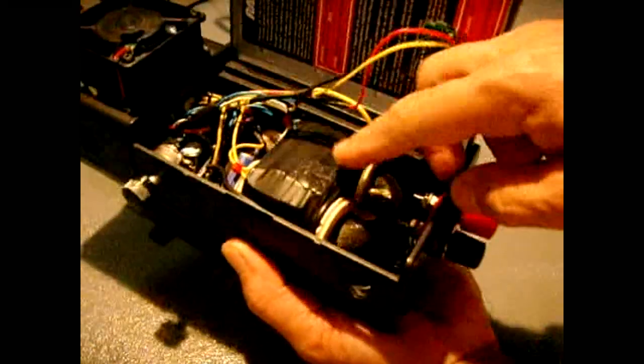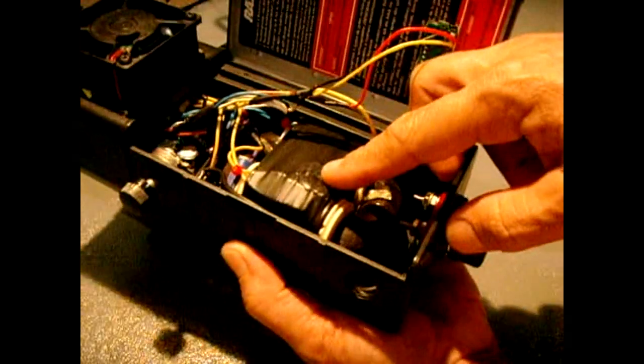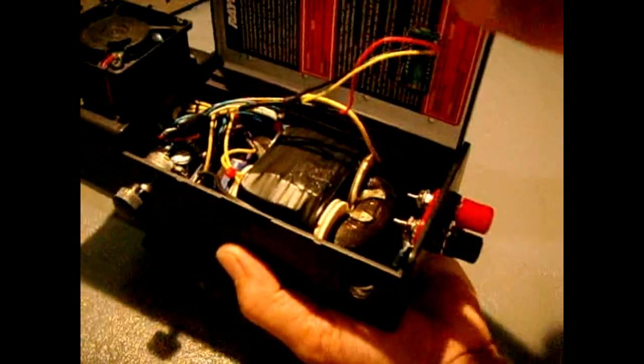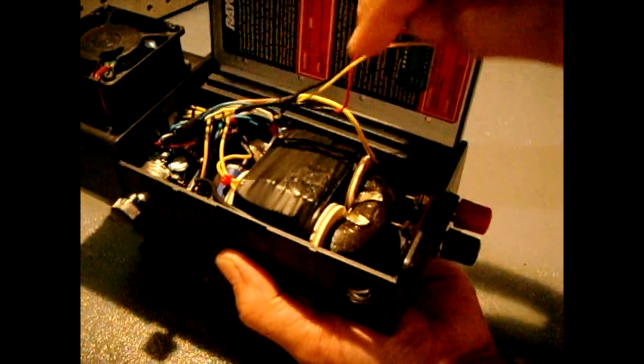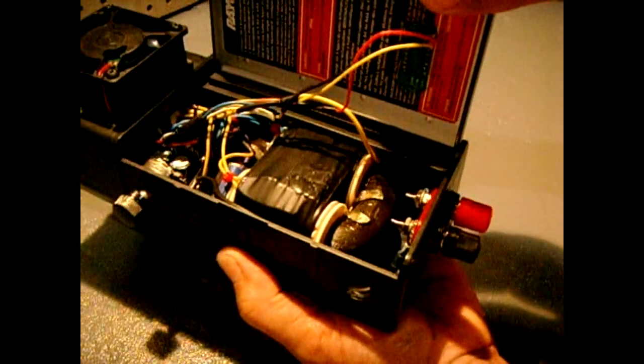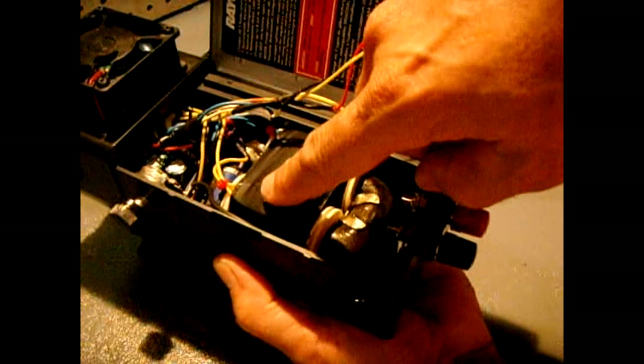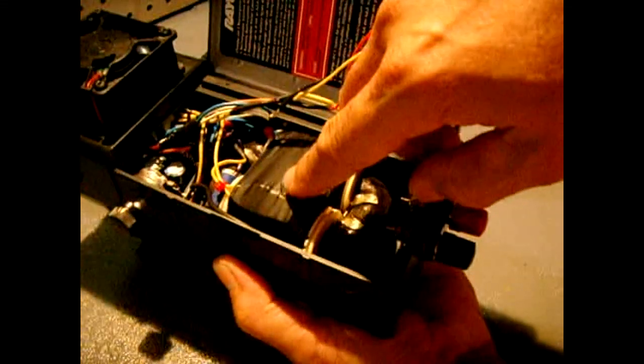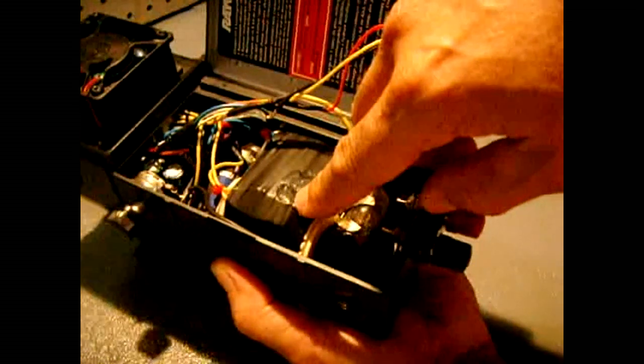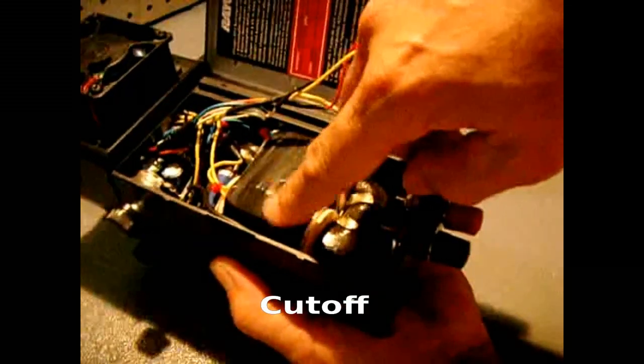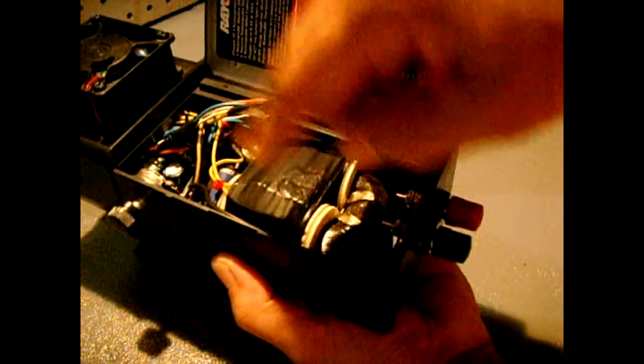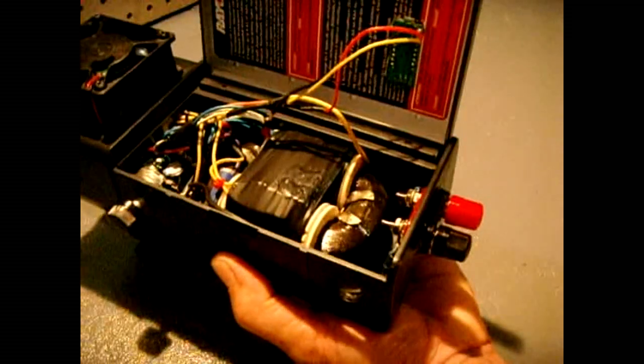Now this transformer runs fairly cool, it gets only a little warm if there's no load on it. When there is a load it's completely silent, I don't hear a thing. When there's no load there is a little bit of a buzz or a hum that comes off of it which is no big deal. Now for thermal protection right against the primary coil pushed very tightly with thermal compound is a thermal switch. It's rated at 150 degrees Fahrenheit. In the event this coil gets too hot the switch will open the circuit turning off the transformer to allow it to cool. Once the transformer's cool the circuit will power back up again.